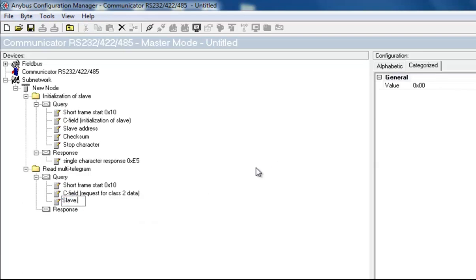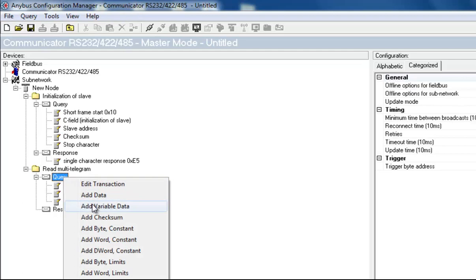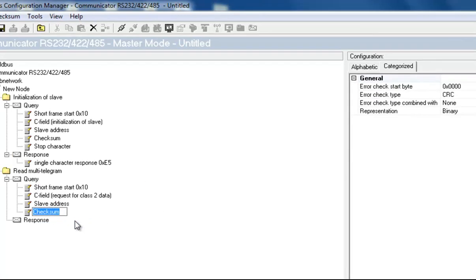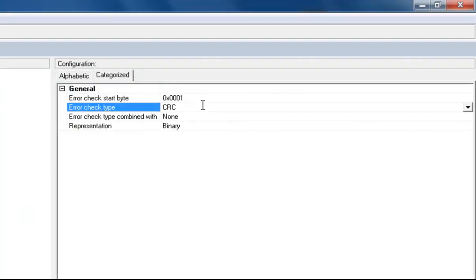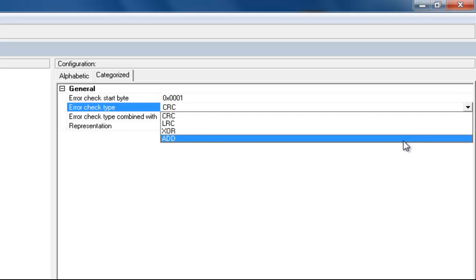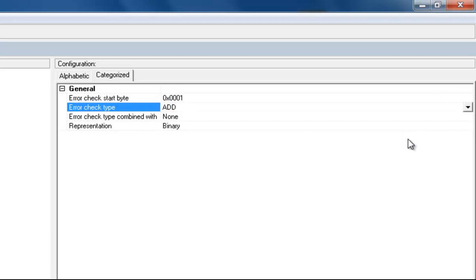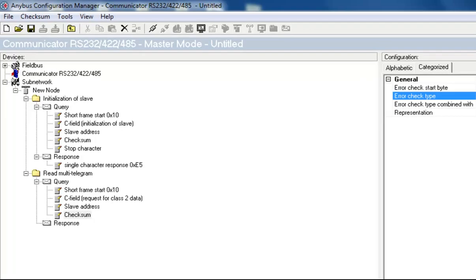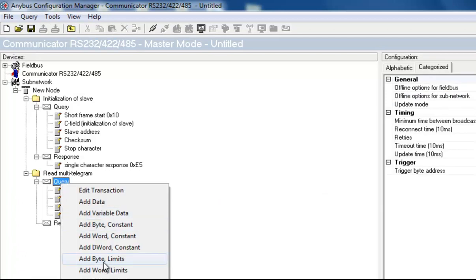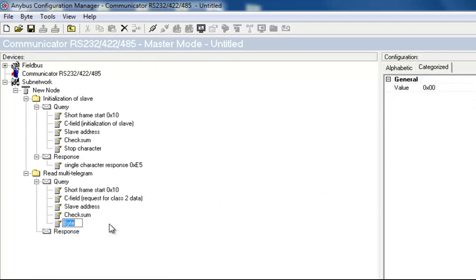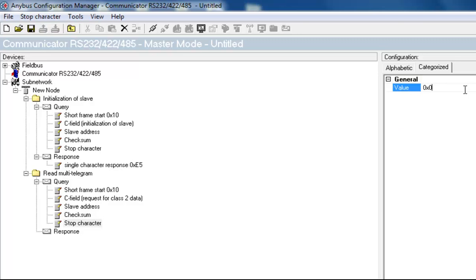I set the slave address to 1, and then create a checksum with the error check start byte 1. I also change the error check type to add. Finally, I add a stop character, which is 16.